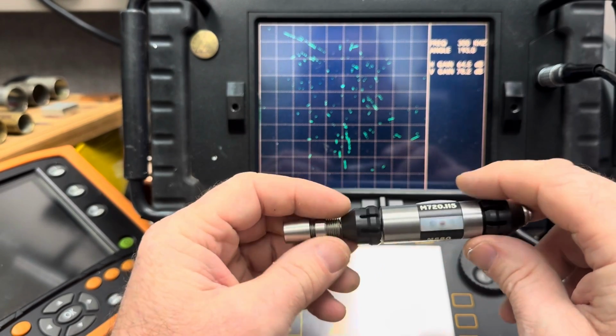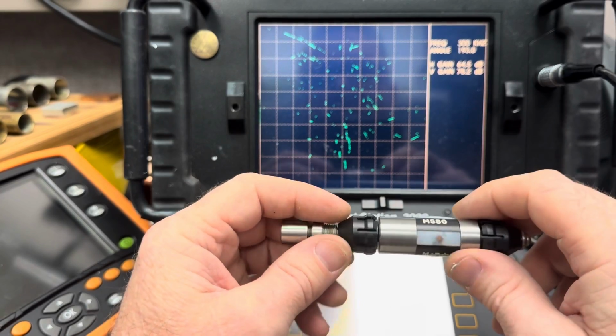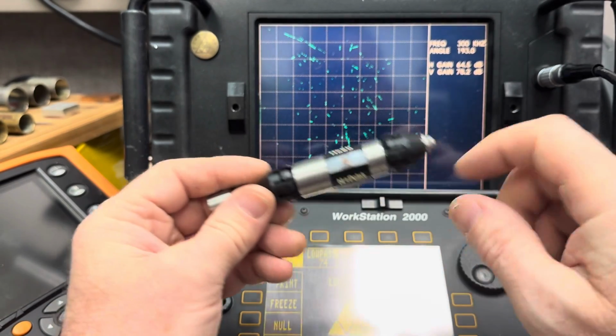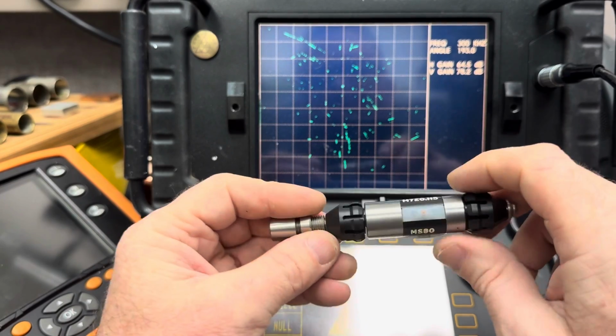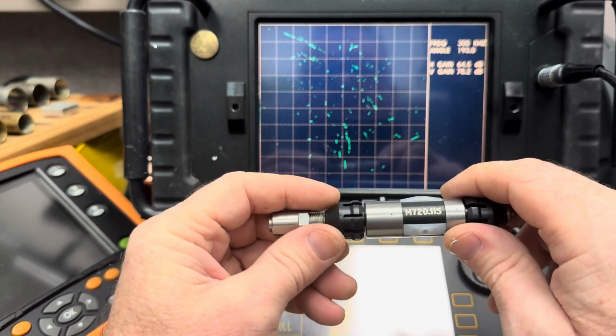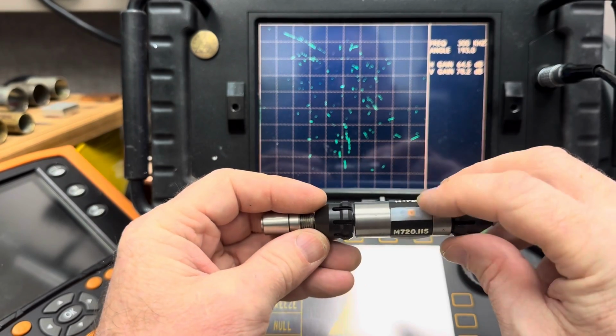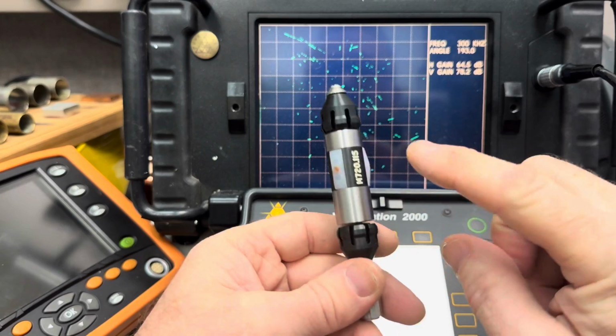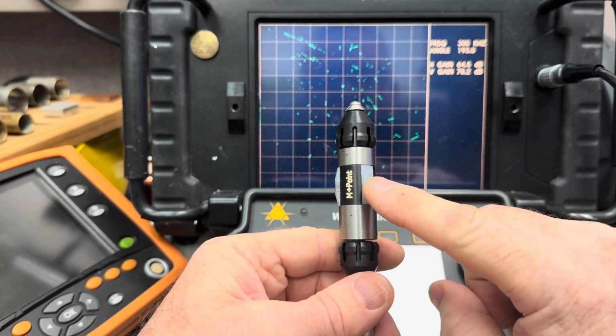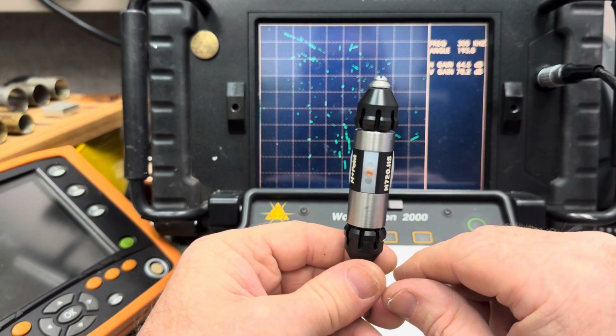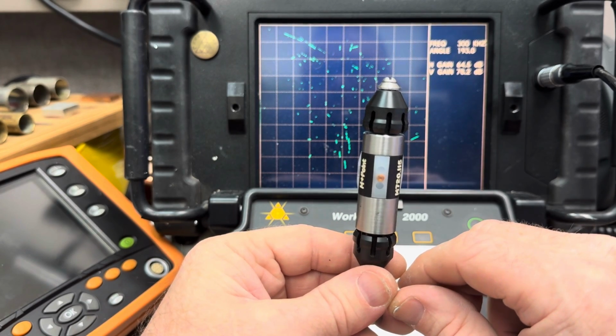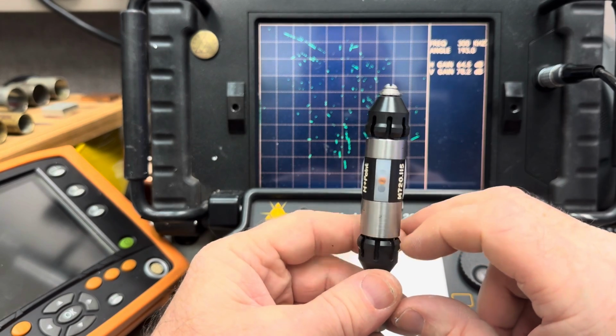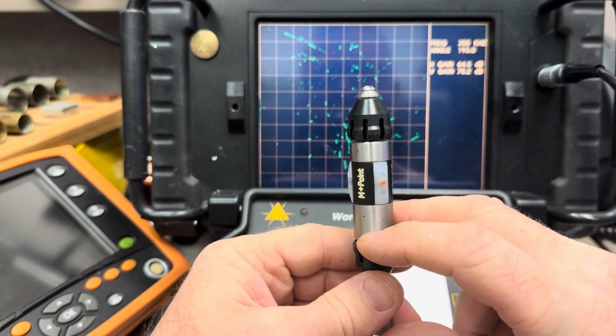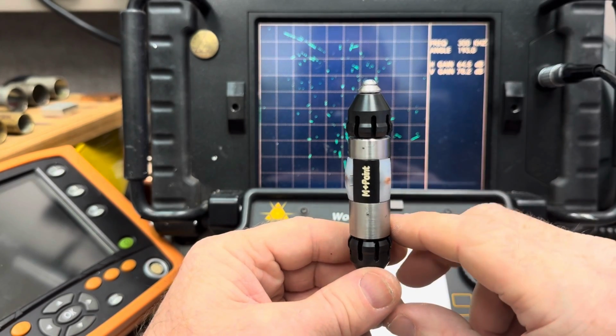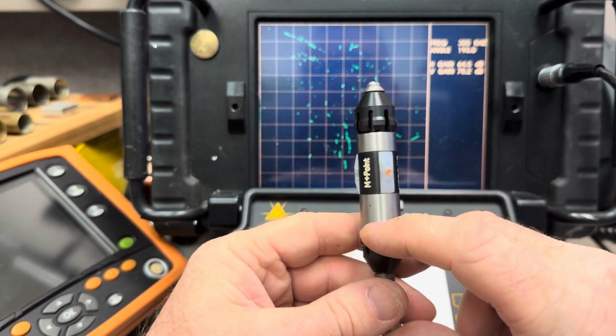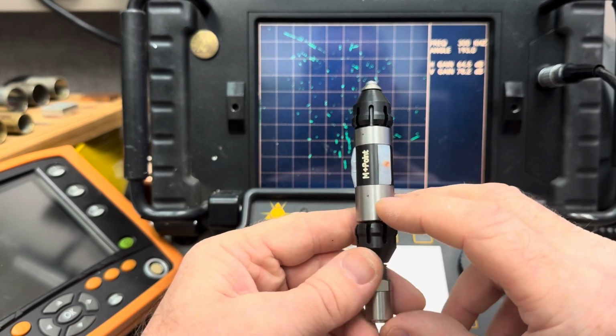If you calibrate a particular plus point channel and vector axial flaws to go up, circs will go down, and vice versa. And then we've got a 115 pancake. That's just a pancake coil like you'd find in pencil probes. So, rotating coil exams are surface exams. Just because you stick this probe up inside the tube, you don't calculate fill factor. Fill factor is only for bobbin coils, which are inside bobbin probes that have the circumferential windings that are non-surface riding. That's when you have to calculate fill factor, 70%, 80%, or whatever.